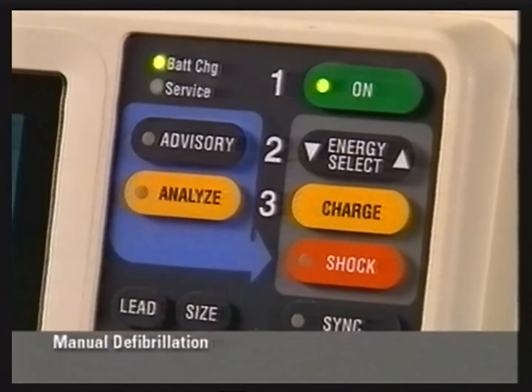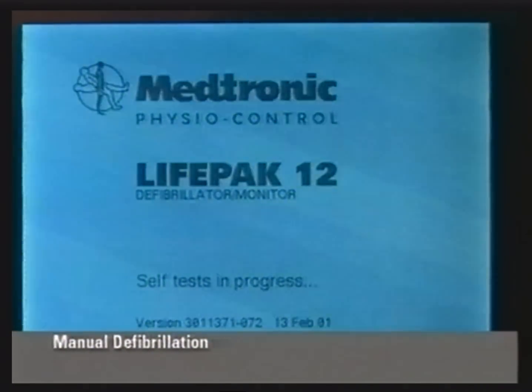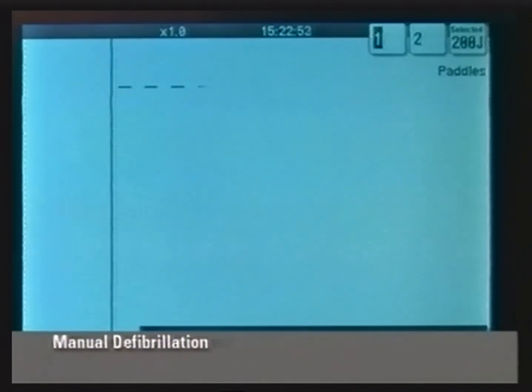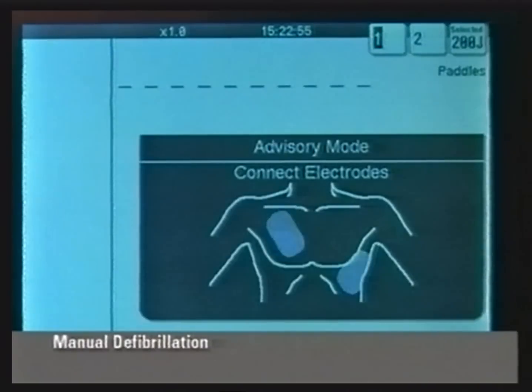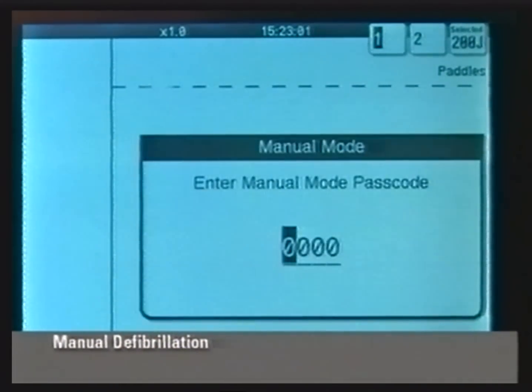To use the Lifepak 12 defibrillator monitor in manual mode, it is important to know if your defibrillator is configured to power on in advisory or manual mode. If the defibrillator powers on in advisory mode, access to manual mode may be restricted. It is important that you are familiar with and understand the power on defaults set on your particular defibrillator.